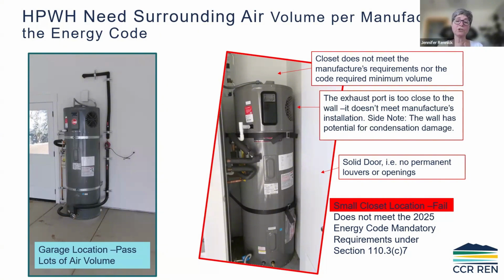And also the space itself is so tight that the exhaust port is really too close to the wall. So what'll happen in a lot of climate zones, even in a relatively dry climate, is there's still enough moisture in the air that when that wall gets really cold from the exhaust air, you can get some condensation issues. So that's what we're seeing to really look out for: just give yourself enough space.